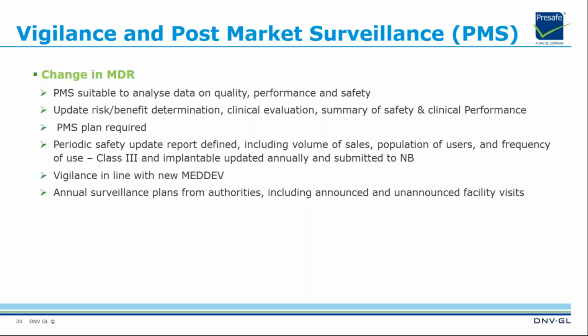Periodic safety update reports are defined, including volume of sales, population of users, and frequency of use, for Class 3 and implantable devices, updated annually and submitted to the notified body. Also, vigilance in line with the new MedDev and annual surveillance plans from the authorized body, including announced and unannounced facility visits.